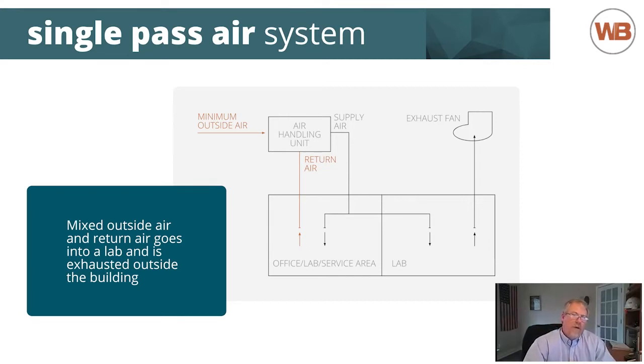Because if you have a bioburden concern, or worry about biologics floating from one space to another, you're subject to a problem when they mix at the air handling unit and potentially take live bacteria or cells from the office or lab area on the left and send them to the lab on the right. So the challenge is understanding, in your building master plan, the limitations of the mechanical system you may suggest or provide as a concept to your tenant.